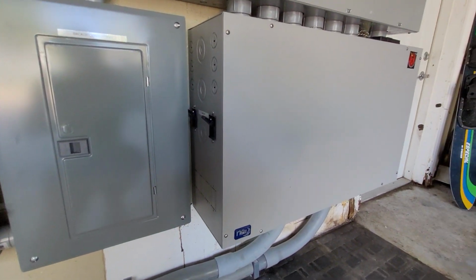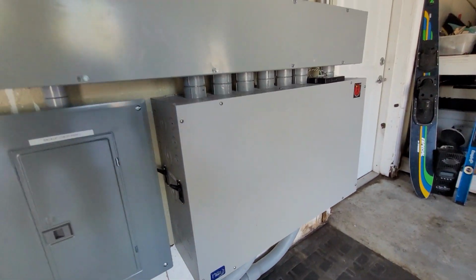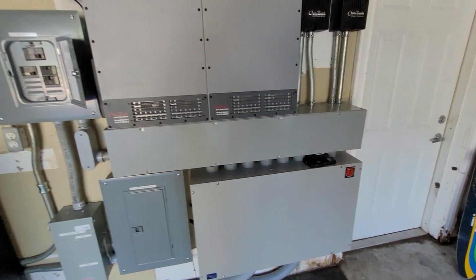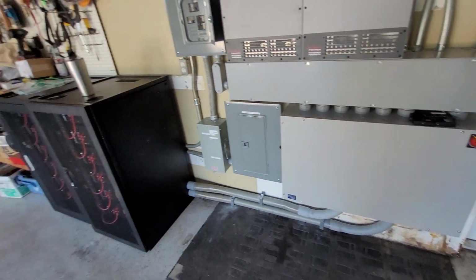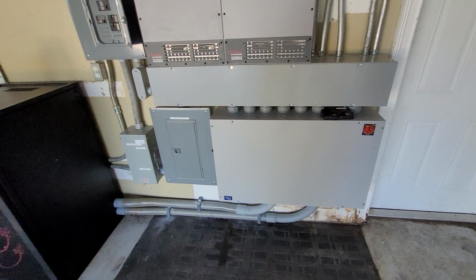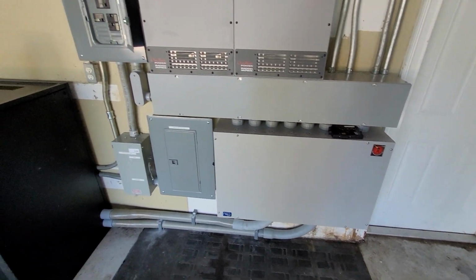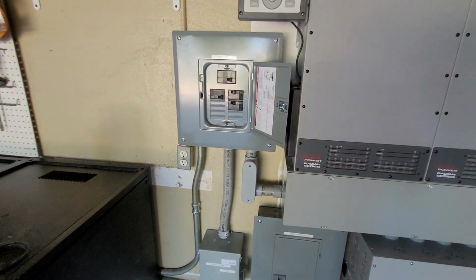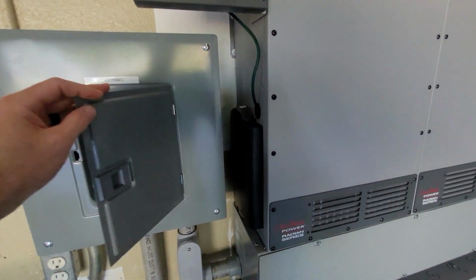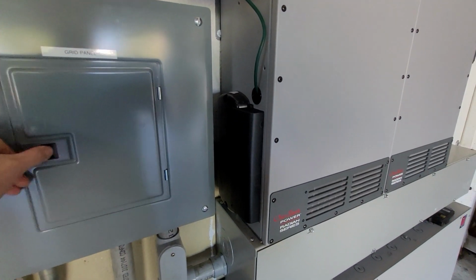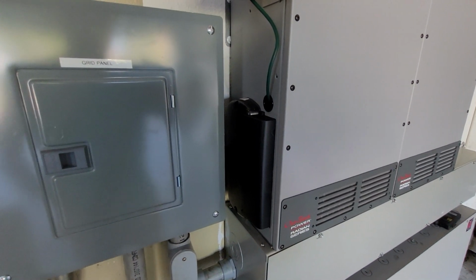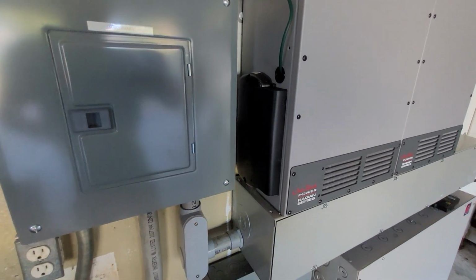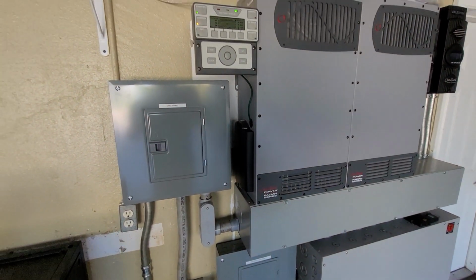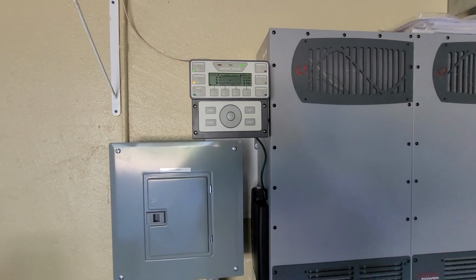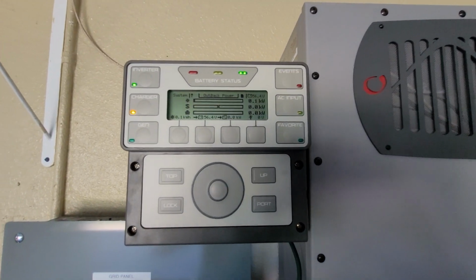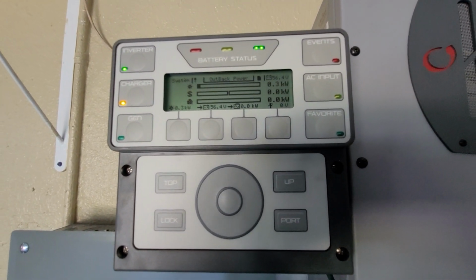And this is just a 1000 amp battery combiner for combining these two inverters and all the batteries. And we're still waiting on another new hub so that we can hook up the battery monitor. This one, we replaced an older Outback system here with this. So that's it in a nutshell, what a frequency shift AC coupled system should look like when it's operating.